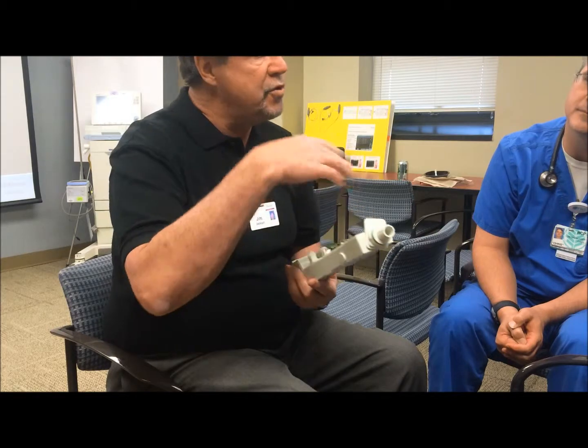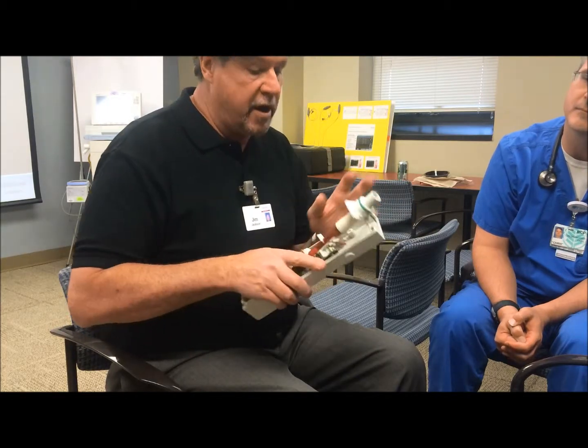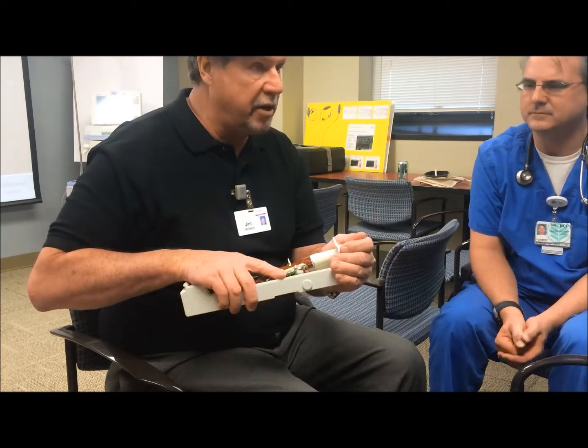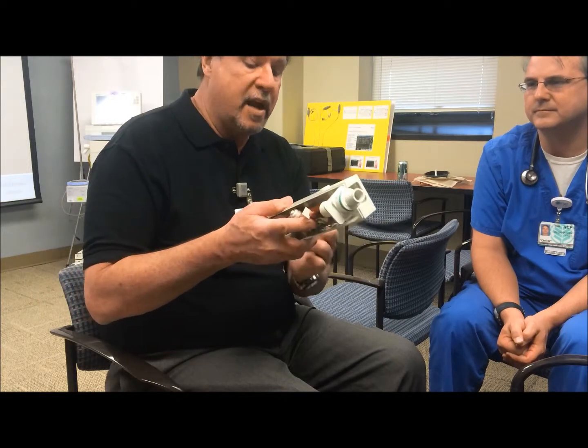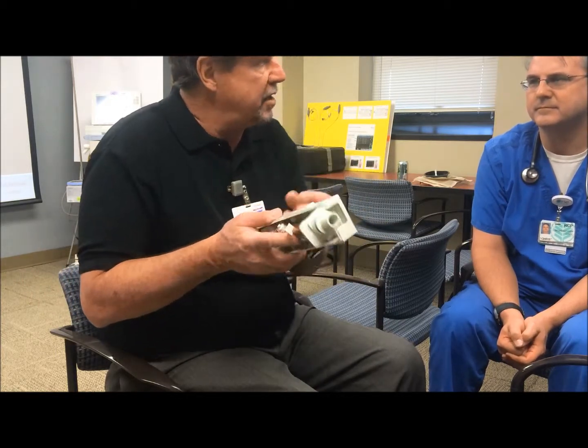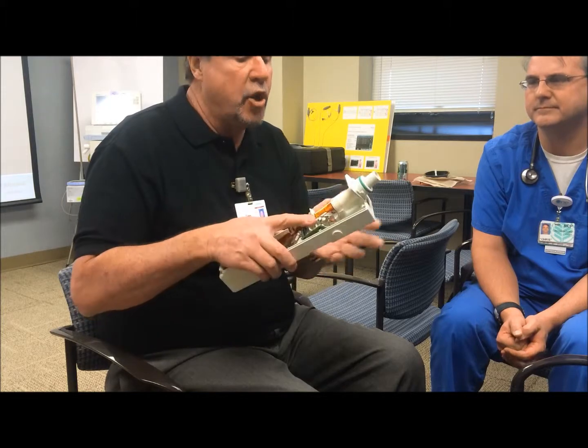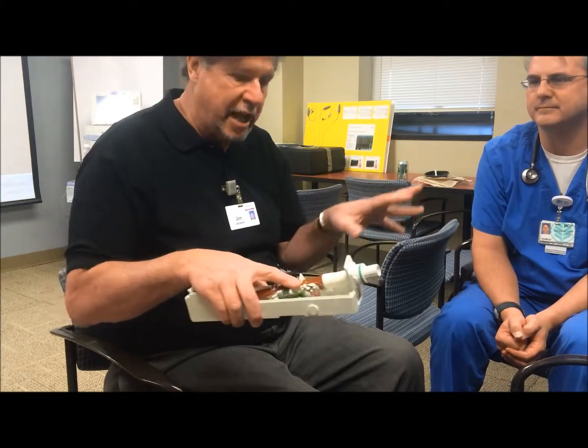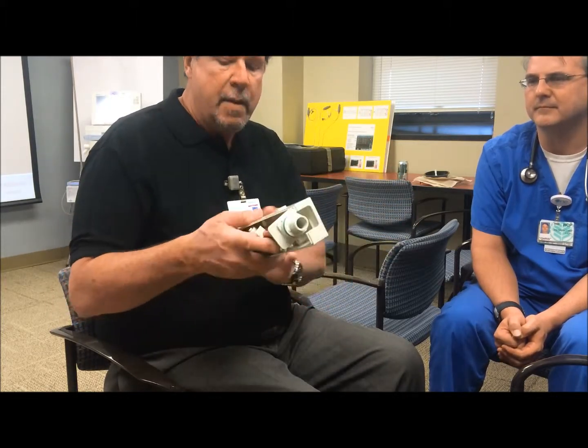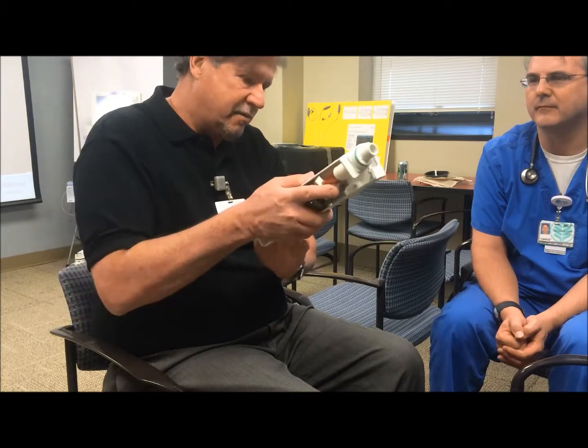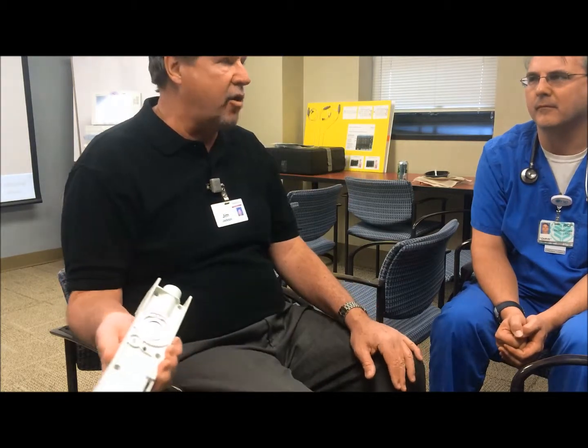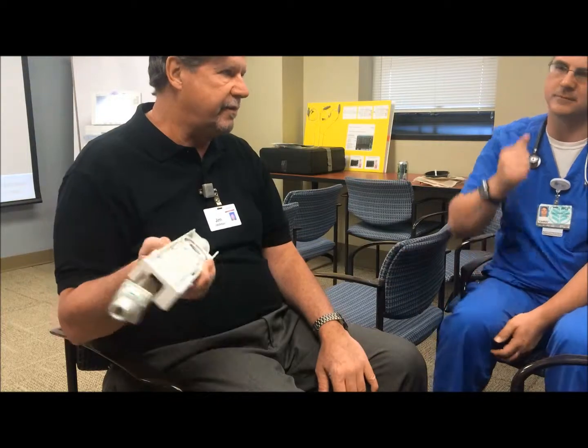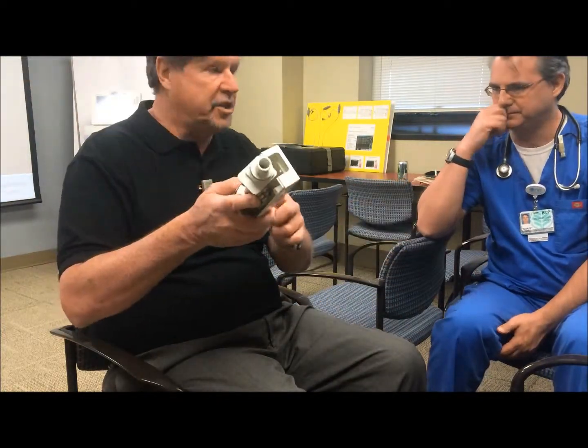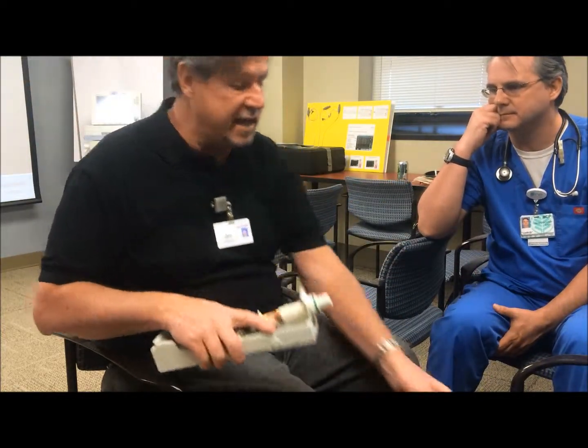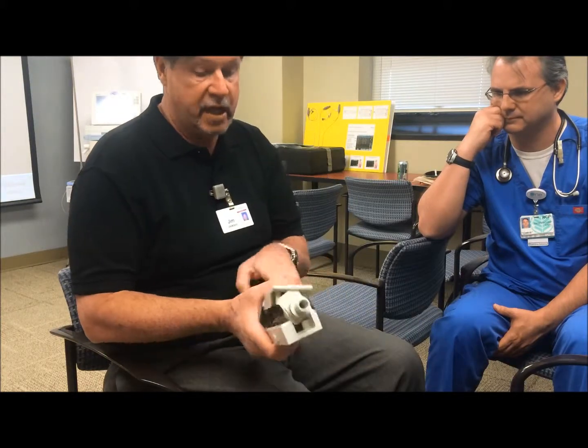Now, if you did have a leak and you say, no, there's no water there, nothing's broken, it could be that on the other side of this membrane there are some crystals. So the only way that you, from a general standpoint, can clean it is to assume that's the problem. Just soak it in alcohol for a good few hours, and that'll dissolve, and then rinse it real well. You can take these cassettes over to the sink and run water through them this way, and water will pour out.